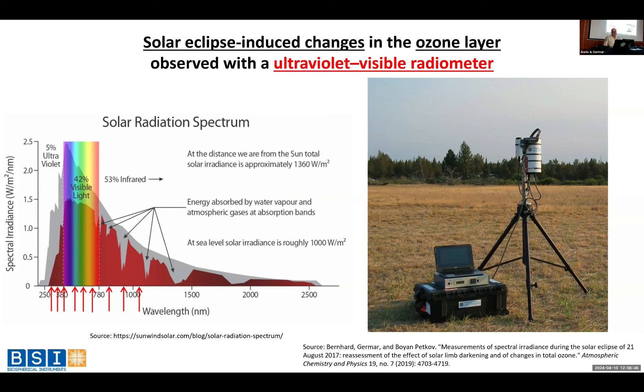The unique thing about the instrument I'm using, which was installed on the roof here just a few days ago, is that it has a dynamic range of 10 orders of magnitude. That means it doesn't saturate when it sees radiation during noon, but I still have plenty of signal when the sun is occluded by the moon. I can actually see the spectrum of moonlight at night with this instrument. It's called a GeoVis 3511 radiometer, made by my company, Biospherical Instruments in San Diego.